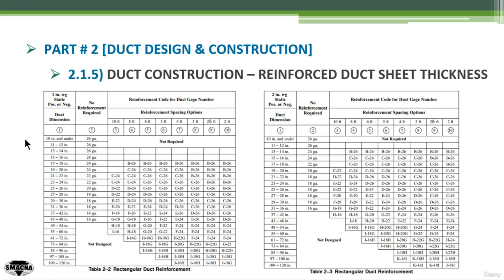For example, for a duct of 50 cm by 30 cm, or 20 inch by 12 inch, I'm going to go through the duct dimension in the first column. The 20 inch is located here, so I go to the next, or the second column, which is the no-reinforcement-required column.